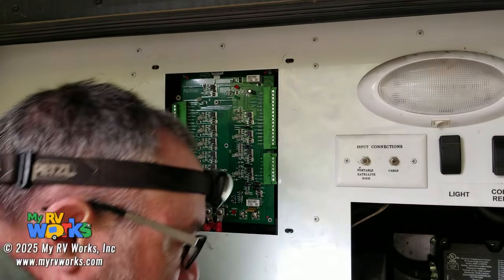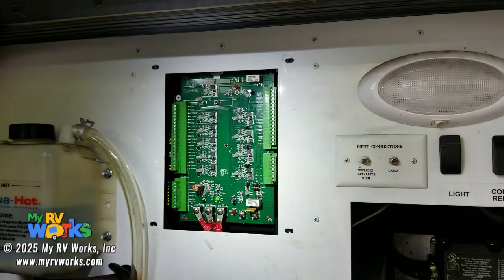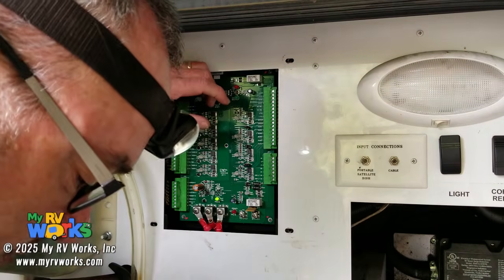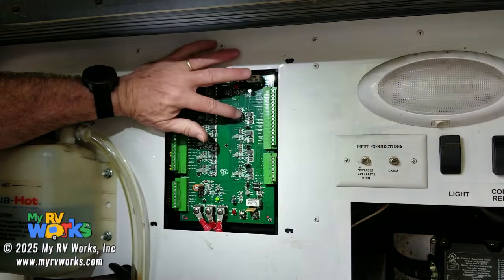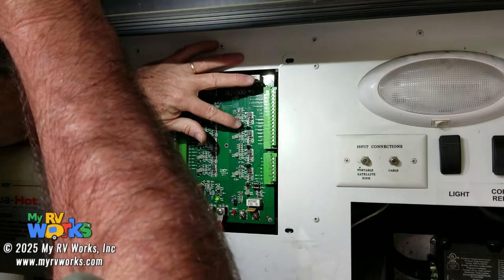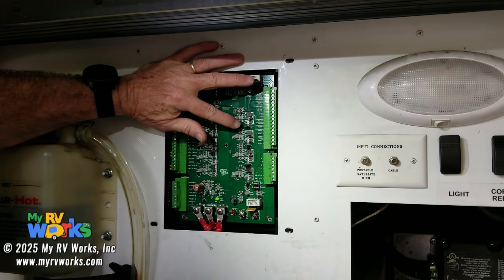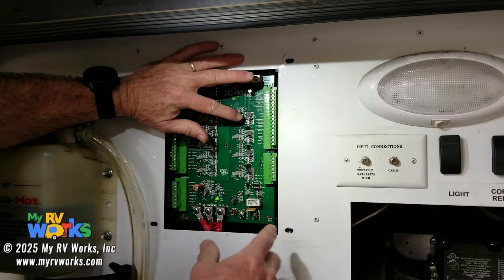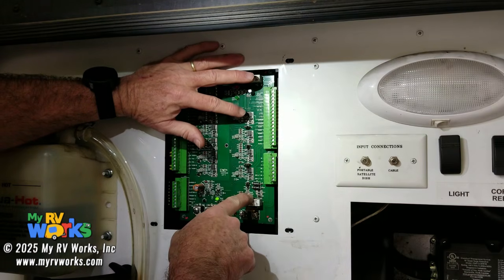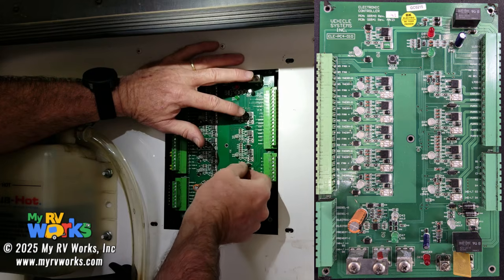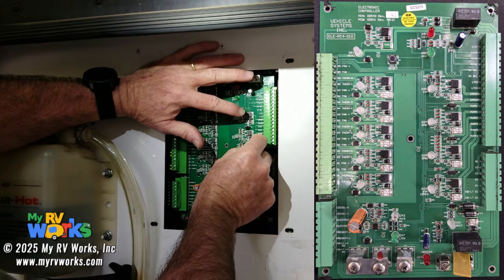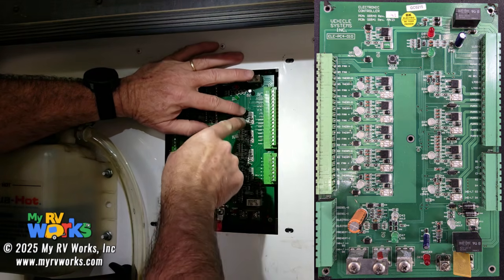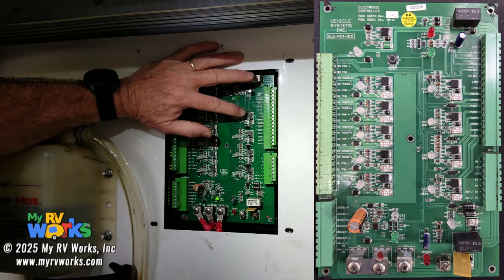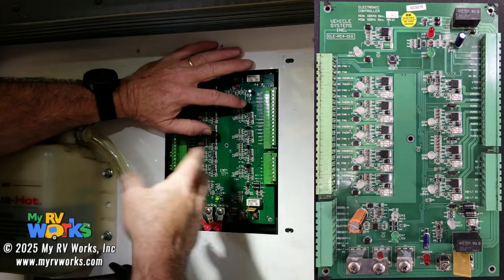So it's a good idea to have the service manual for reference. When you get a copy of it and you're wondering what's going on, sometimes it's good just to make sure these jumpers are in the right place, that they haven't fallen off, and that they're connecting the right two pins. Because if the jumper configuration is set for a 650 and you have a 450, you're going to have a problem with it understanding what it's doing.